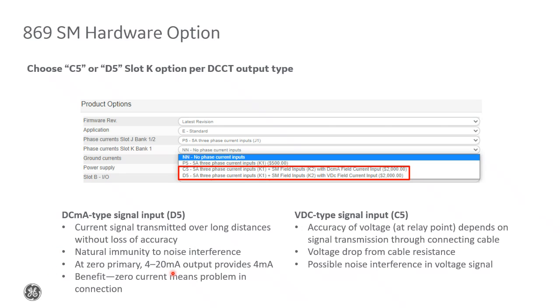So if you're using a 4 to 20 milliamp signal, if that output's showing 4 milliamps at the relay, we definitely know it's a zero reading. But if at the relay you're seeing 0 milliamps, then we know for sure there's probably an issue with the CT cabling itself. So that's very helpful for troubleshooting purposes.